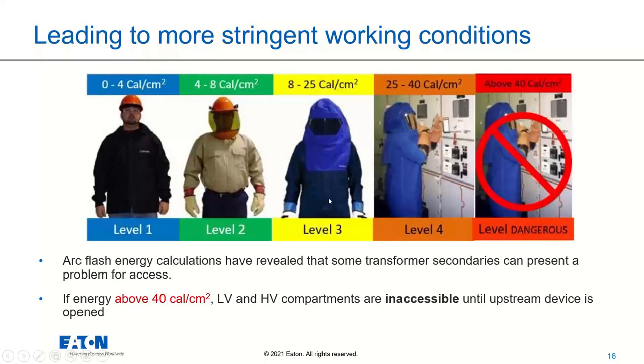In reality, if I was working on a transformer secondary and I had that HCB, that horizontal conductors in a box, I might be about 190% of that, at the greatest degree. And I actually might have been over the 40 calorie limit. So in terms of what OSHA dictates and this cutoff of 40 calorie, that still exists. All the tests were done with those actual energy values. But what's changed is our understanding of how that arc propagates and what the resultant calorie level is.